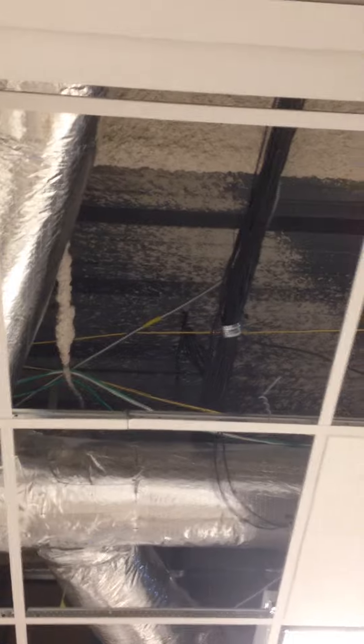You can see the cable up there — J-hook as it crosses over the air duct. We've got our path defined here as we go from J-hook to J-hook. We're using plenum rated cable as well as plenum rated ties — everything that's got a fire rating since this is a drop ceiling, which is something you want to take into account if you're going to get network cabling with a drop ceiling.